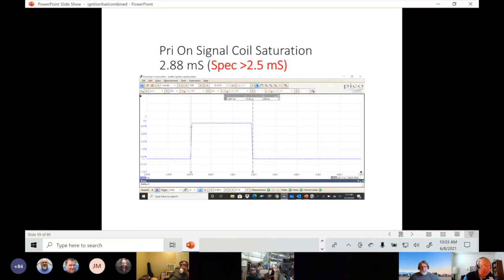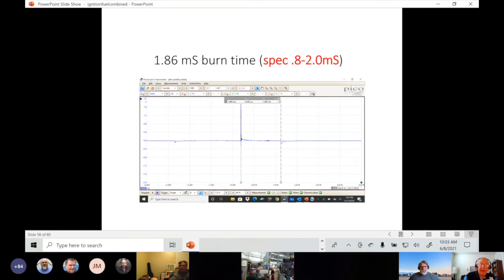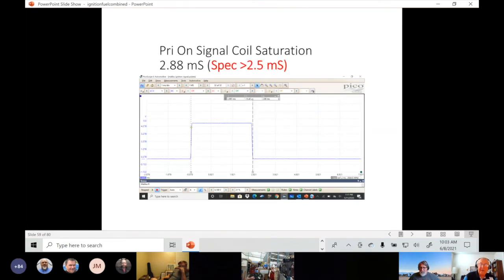Now let's switch gears here a little bit. That was burn time, and there's an actual spec for it. The next thing is coil saturation, and there's an actual spec for this too. This coil saturation is 2.88 milliseconds, and the spec is in red. So the specification is greater than 2.5 milliseconds, and we're running 2.88.